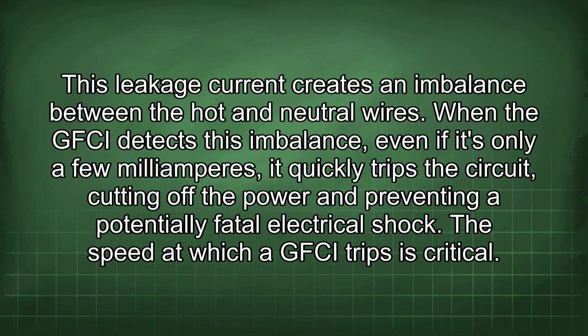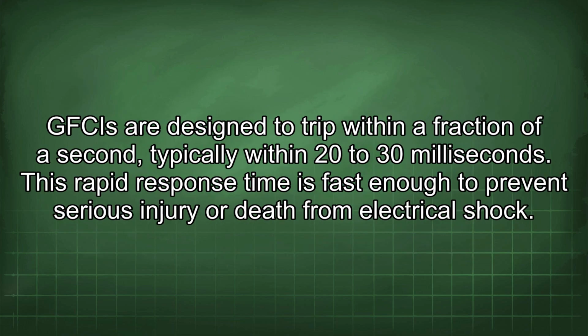This leakage current creates an imbalance between the hot and neutral wires. When the GFCI detects this imbalance, even if it's only a few milliamperes, it quickly trips the circuit, cutting off the power and preventing a potentially fatal electrical shock. The speed at which a GFCI trips is critical. GFCIs are designed to trip within a fraction of a second, typically within 20 to 30 milliseconds. This rapid response time is fast enough to prevent serious injury or death from electrical shock.